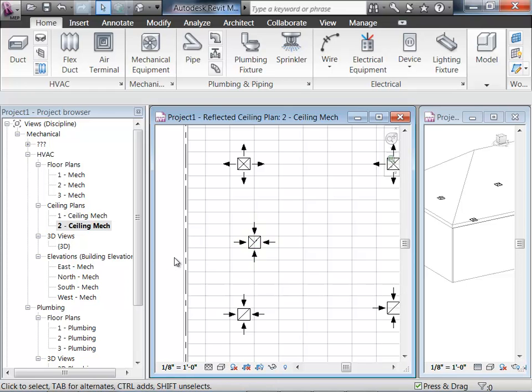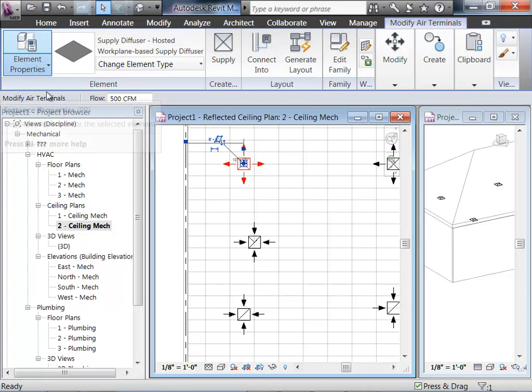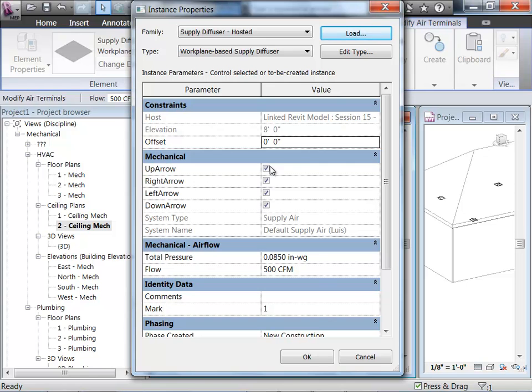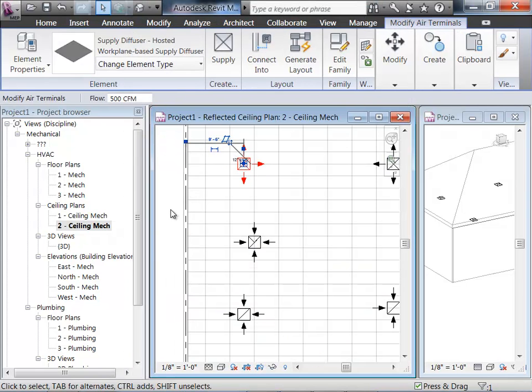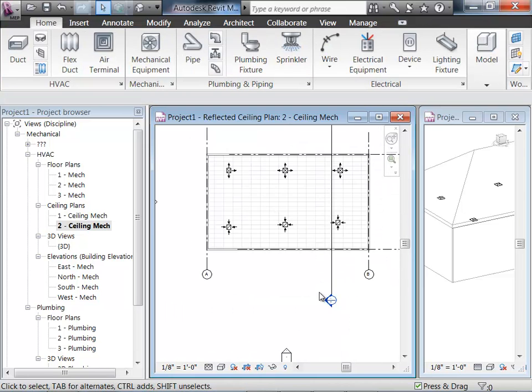Another thing you'll notice is these little arrows. The supply arrows are pointing out, signifying that this diffuser is going to blow air in all directions. So if you have a supply diffuser up against a wall, you don't want to blow it at the wall. To illustrate: select the supply diffuser, go to Element Properties, Instance Properties, and you have an option of deselecting one of the arrows — say the left arrow. Now you can see how it removed that direction. I'm going to delete this exhaust grill because we really don't need it at this point.